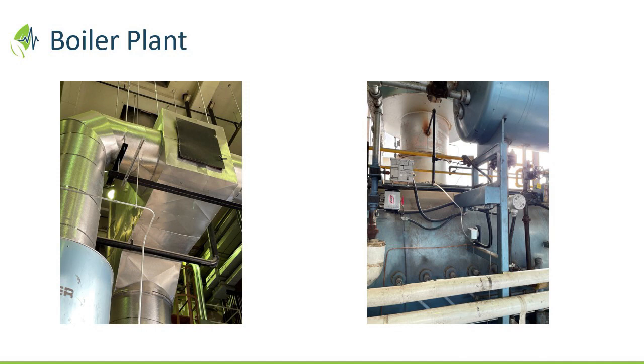You mean like injecting urea into the stack? Well, no, in terms of the water system. Well, water's funny. We used to get a lot of flak because a low volume boiler requires clean water, but if you want clean combustion and to decarbonize, you must run an exceptionally clean water system. Okay, thanks. Not just boilers, heat exchangers too, all of them.